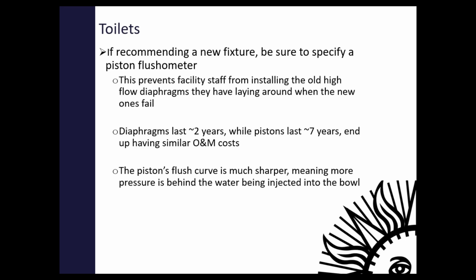Another, I guess, quicker way to do it, if you're just trying to estimate very quickly, you can count the number of seconds that a commercial fixture flushes and divide that by 2, and that will give you a general sense of the GPM that fixture is flushing. So for a 1.6 gallon per flush toilet, you'd expect it to take a flush time between 3 and 4 seconds. That's just kind of a general rule of thumb, kind of loose, but it can get you a quick estimation. Thanks. That was good.